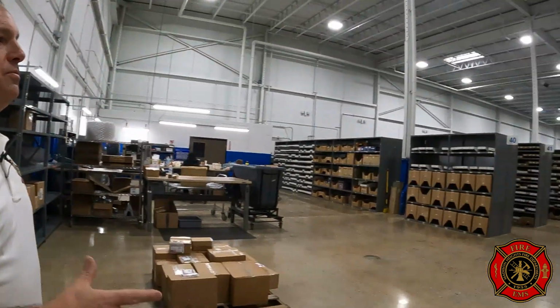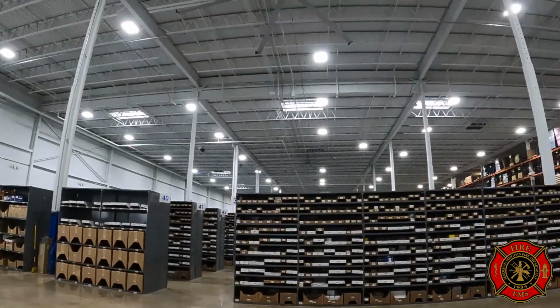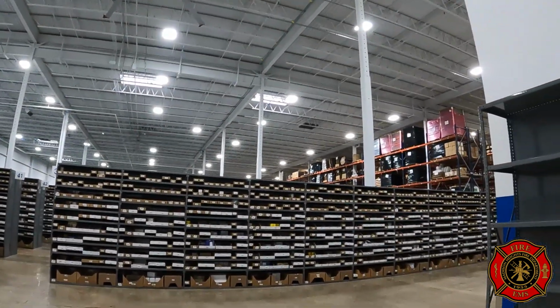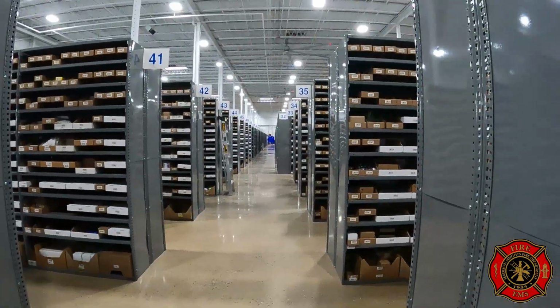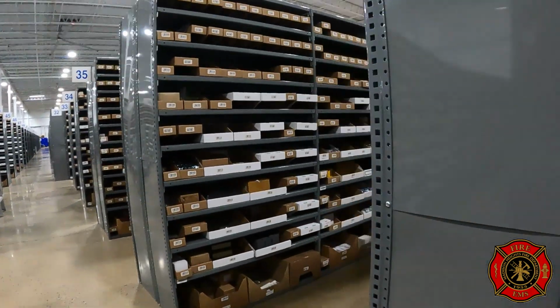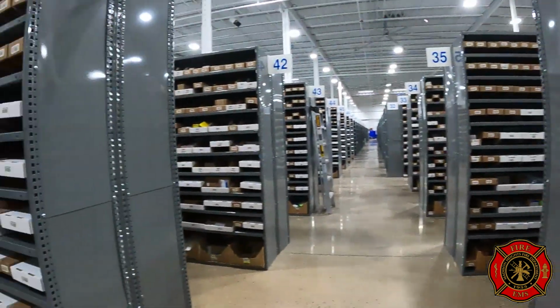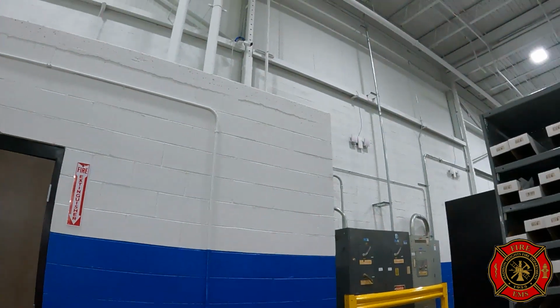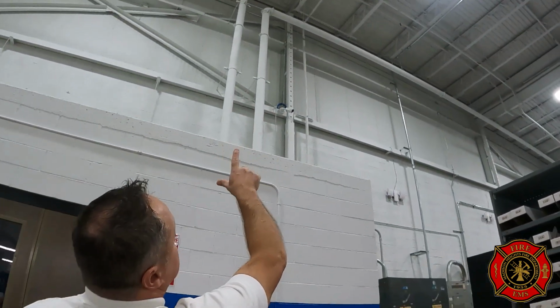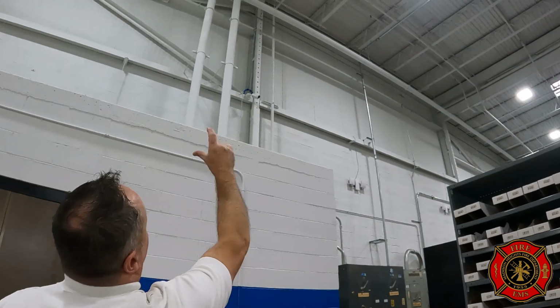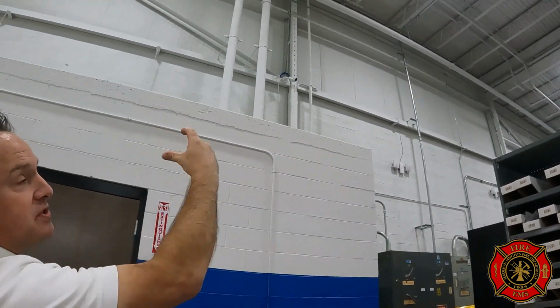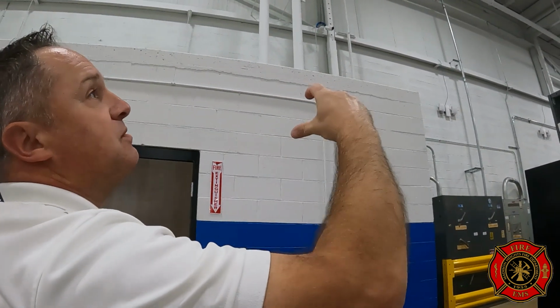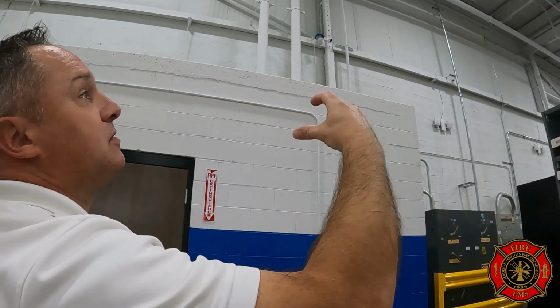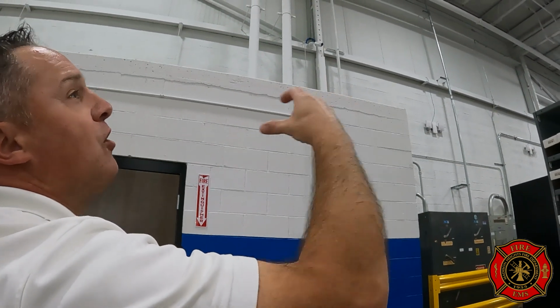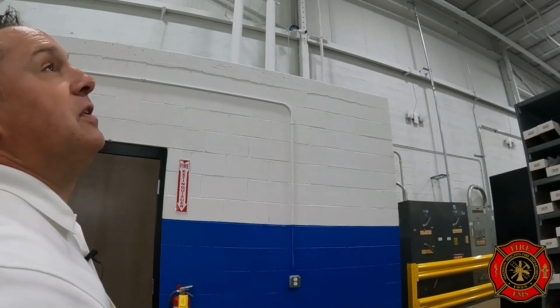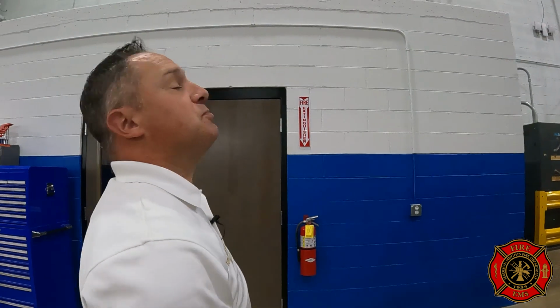So as we look around, we see that they do a lot of storage inside here. We want to make sure that their aisle widths are wide enough that people can go in and out. While I'm walking, I'll look at the ceiling and look at their sprinkler system. The gold or brass colored protrusions out of the pipe there are the sprinkler heads. We want to make sure that there's no corrosive substance on them, and that they're not painted, which would interfere with the function of the sprinkler head.